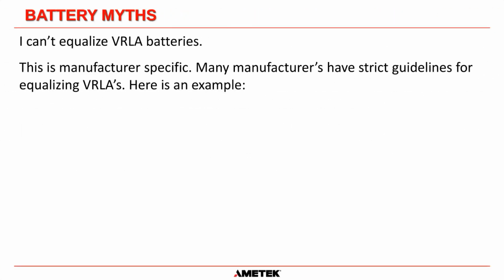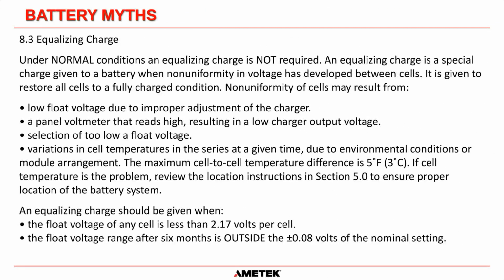Another battery myth: I can't equalize VRLA batteries. I can't equalize valve-regulated lead-acid batteries. That's not true. It is manufacturer specific, and many manufacturers have strict guidelines on what their equalizing charges should be. And here's an example.